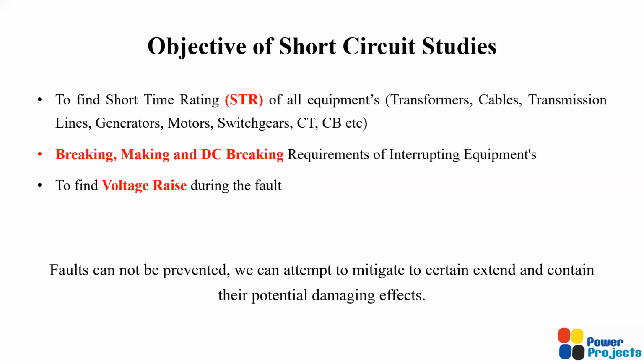As we discussed, there could be an increase in voltage during a single line to ground fault in ungrounded systems or resistance grounded systems or resonance grounded systems. So we have to see what the rise in voltage is during these faults as well.